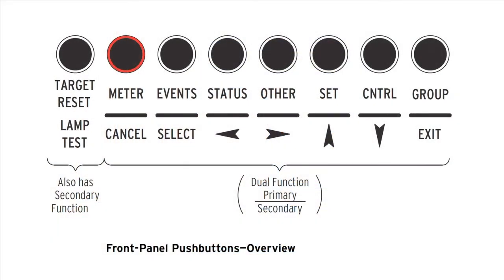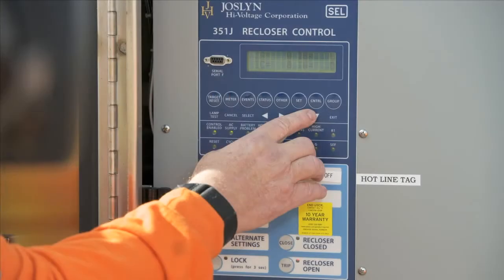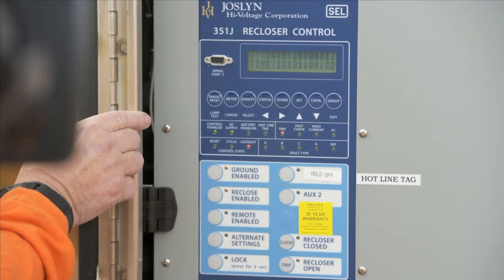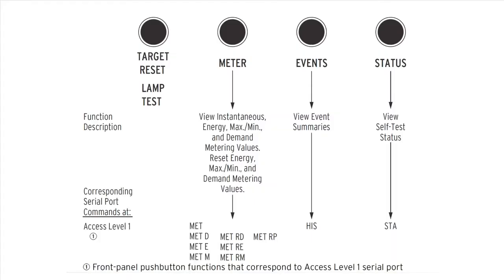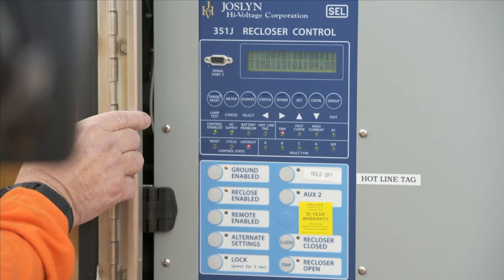Meter. The meter command shows the AC currents and voltages, magnitude and phase angle, which are presented to the relay in primary values. In addition, the command shows power system frequency and the voltage input to the relay power supply terminals. Compare these quantities against other devices of known accuracy. The meter command is also available at the serial ports and front panel display.